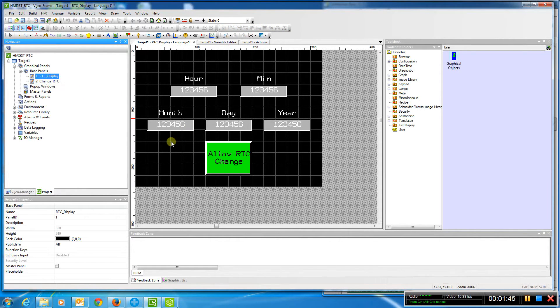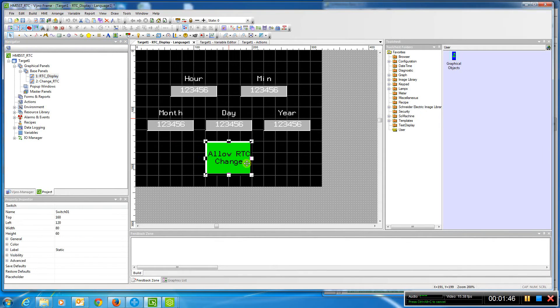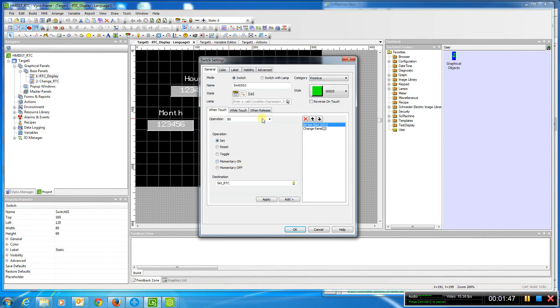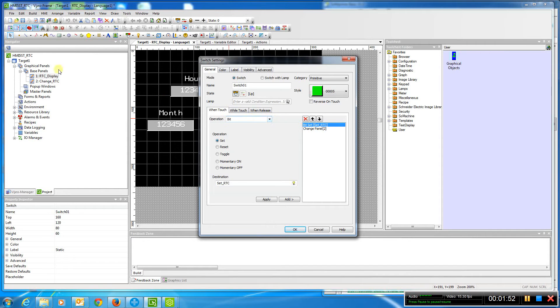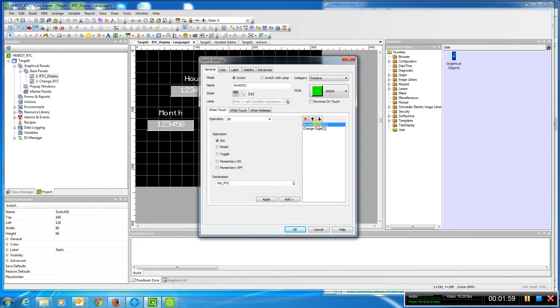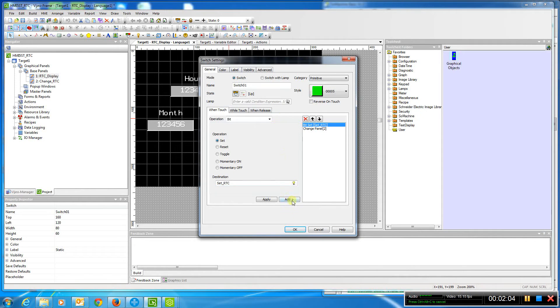We'll go back here. When we do this button change, we're doing two things. When we push the button, we're going to the change RTC panel and we're setting a bit in the PLC that allows it to be changed. So that would actually be M0 in our case, which turns on system bit 50. That allows us to change it in the M221.